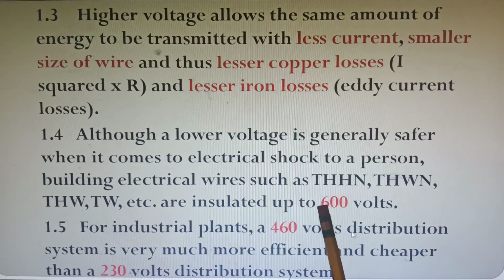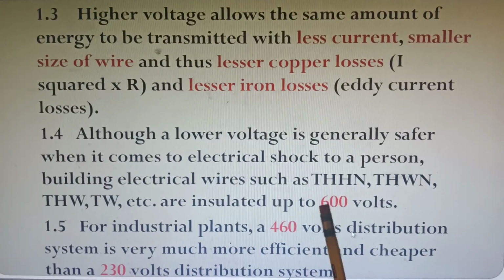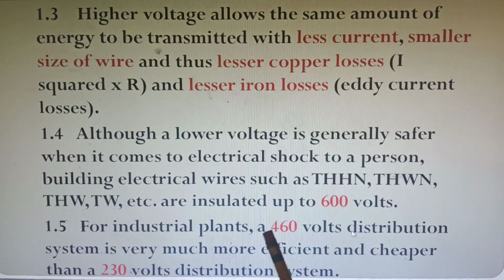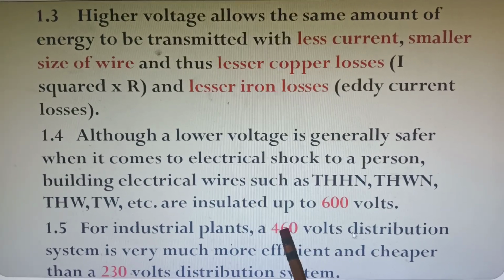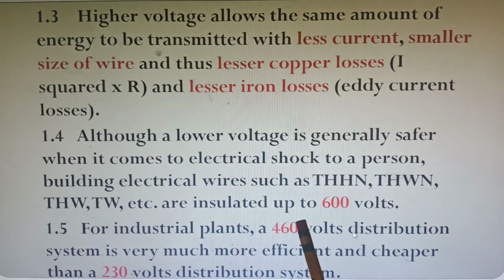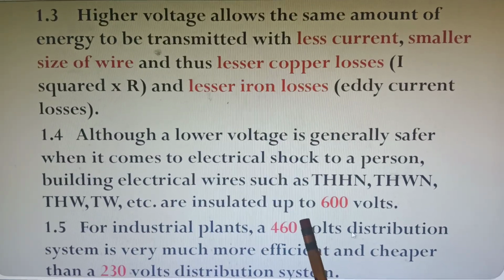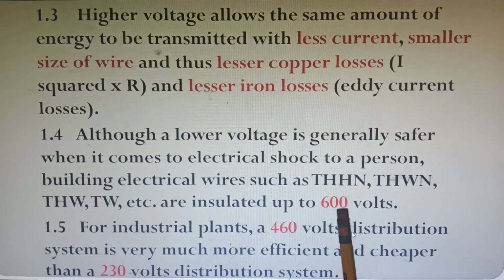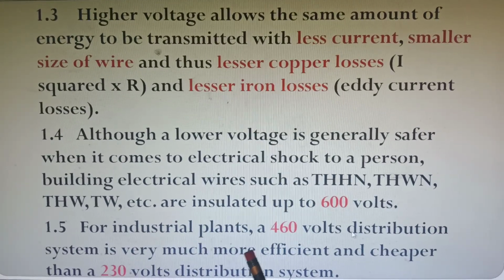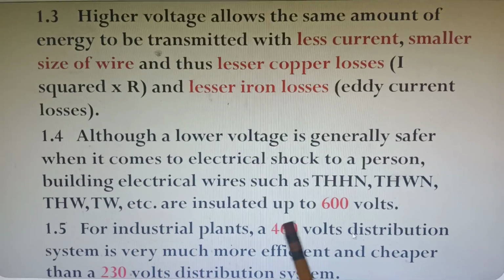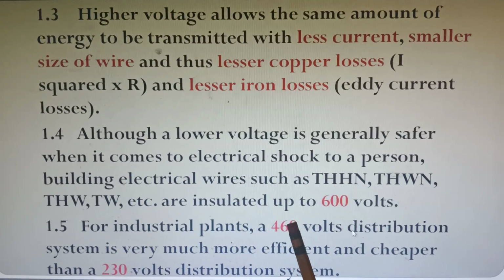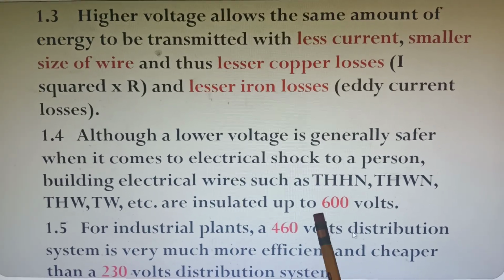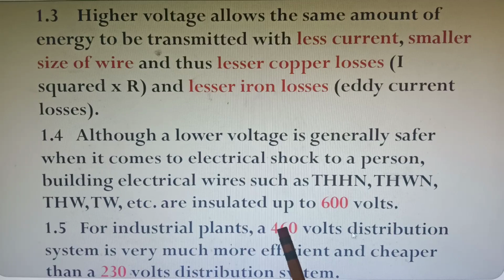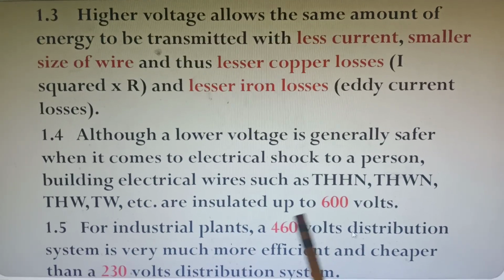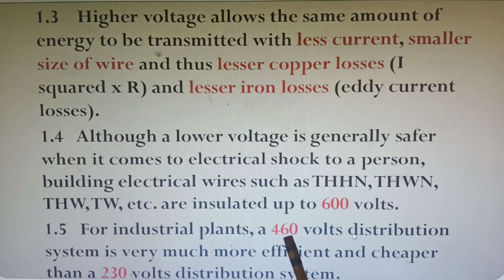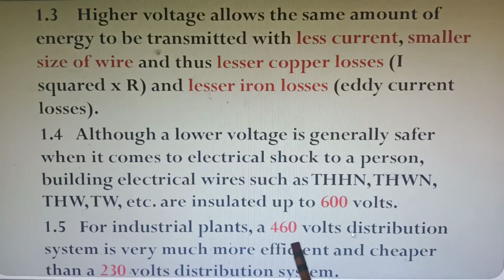The current was so high, with a 2500 kVA transformer and a 230 volt secondary voltage, your current is very high, and therefore it will entail a very, very big main circuit breaker. So that's the problem. So when I was tasked to design a new plant in Santa Rosa, Laguna, I decided to suggest using 460 volts instead of 230 volts.